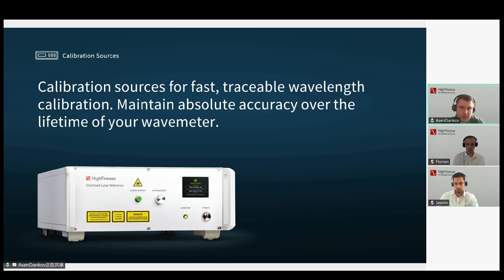Every wave meter needs to be calibrated regularly to maintain its accuracy. How often depends on the accuracy level. Entry-level wave meters only need calibration about once per month, and that can be done using their built-in calibration source. But our most precise instruments need calibration much more frequently, sometimes every few minutes, and this requires an external, highly accurate reference laser, usually stabilized to an atomic or molecular transition. To make it easier for our customers, we offer these reference sources directly. Some, like the SLR 780, were fully developed in-house at HighFinesse. Others we source externally, but we verify their accuracy ourselves before making them available, so customers can trust the whole calibration chain from start to finish.